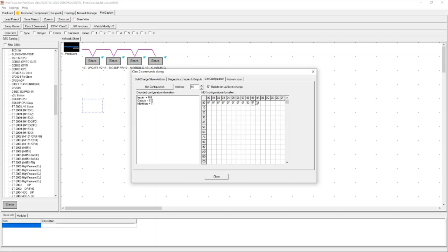This hexadecimal configuration information is essentially how Profibus devices transfer information related to each submodule — how much input and output data that submodule can provide, how the data is to be treated, and whether it's an input or output module. Checking address 11, my four digital input, four digital output module, he only has one byte of input and one byte of output — identified by hex configuration buildup 20, 10. Let's set up that device.